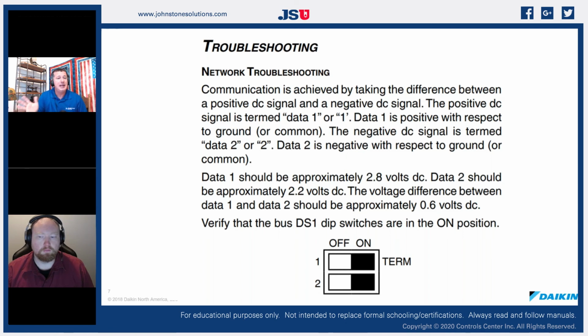A lot of guys and gals will say, hey, why don't we just flip those DS switches on from the beginning? I go, well, it's not there for that. It is a fix for when we need it. So we don't use those bias switches unless we absolutely need them. If we have additional load on our network because of long lines, or we have additional equipment, then we may have to adjust our bias. Because if we walk away from this piece of equipment and we have less than 0.6 volts DC bias between 1 and 2, someone's coming back to work on this thing probably the next time that it rains, because then we're going to have a change in current, a change of load, and we're going to affect the load on that network. So it's critical to have that 0.6 volts bias between the two.